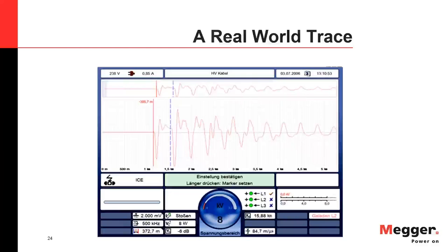What's also recommended on the TDR settings is that you take the gain up, because the signals that you couple with the CT out of the high voltage return are typically of less intensity than with the arc reflection method. So you typically should have more gain on the ICE method. Now, that is pretty much what you have for the flashover faults below 32 kV.